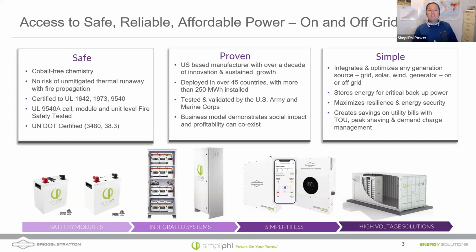Simple, what we've always been founded on, and as you can see down there in the bottom left corner, our batteries really still are inverter agnostic and charge controller agnostic. As long as you take one of our batteries and perhaps you replace some lead acid batteries, get into that inverter, get into that charge controller and adjust the set points so that you're treating the batteries the way they want to be treated. I'm thinking of our float voltages, disabling equalize, the bulk voltages, max charge, max discharge amps.